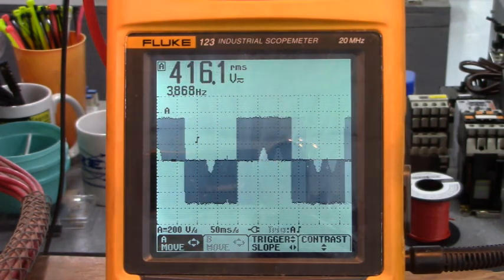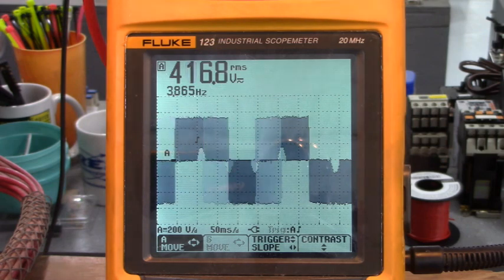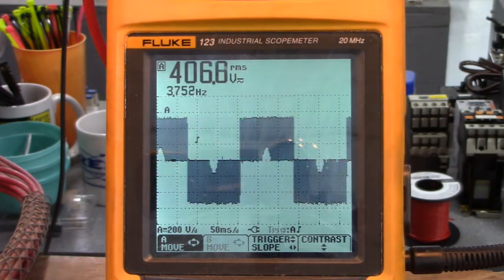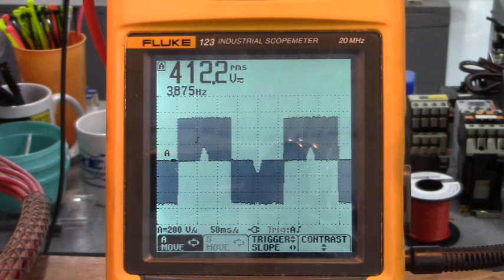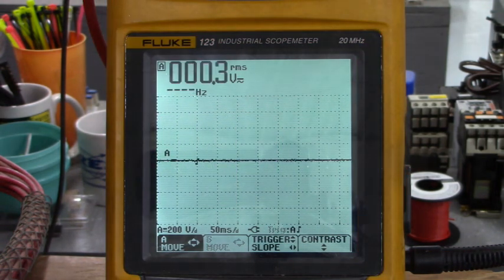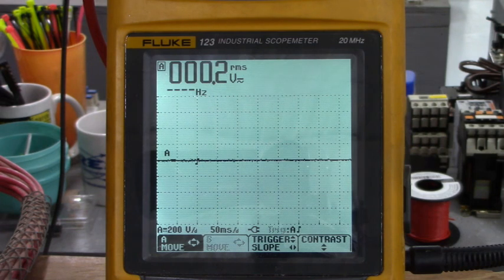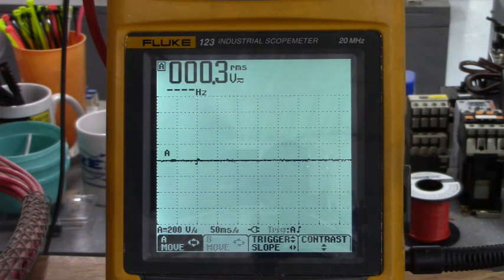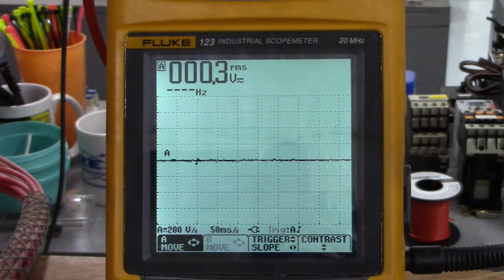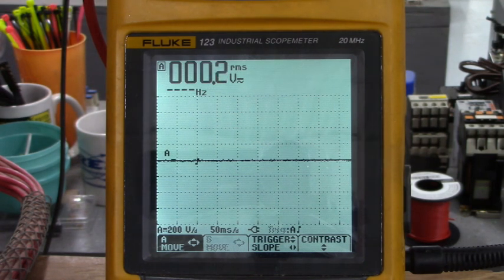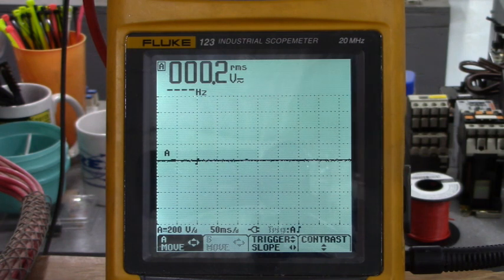I'm going to disable the drive from running, turning off the 24 volts DC from terminal 28 and its ground on 39. I'm going to stop our test DC motor and resolver. Now going to go over and turn the 380 volts 3 phase off from the L1, L2 and L3. And we're going to head to the hooch. Nice.